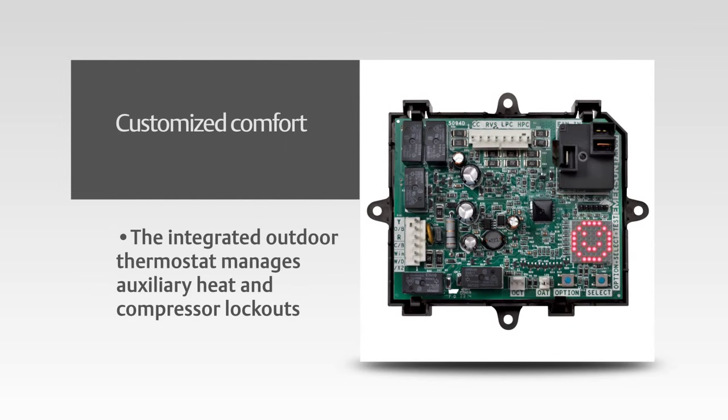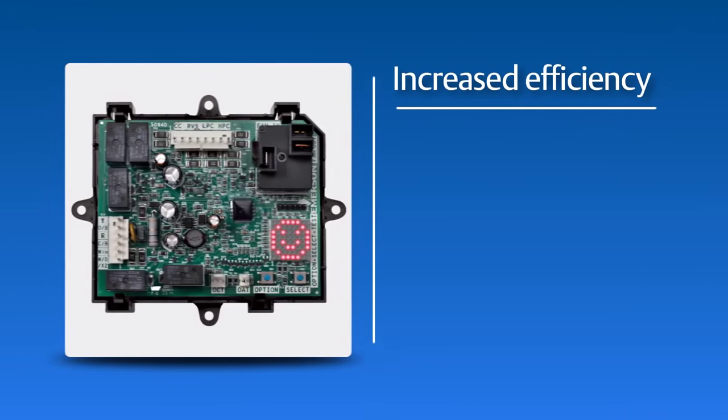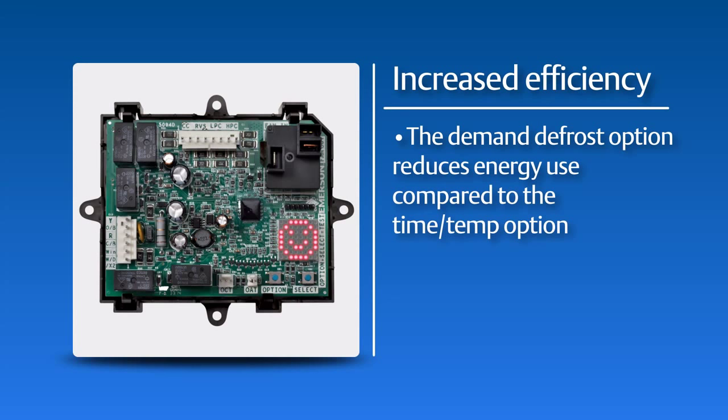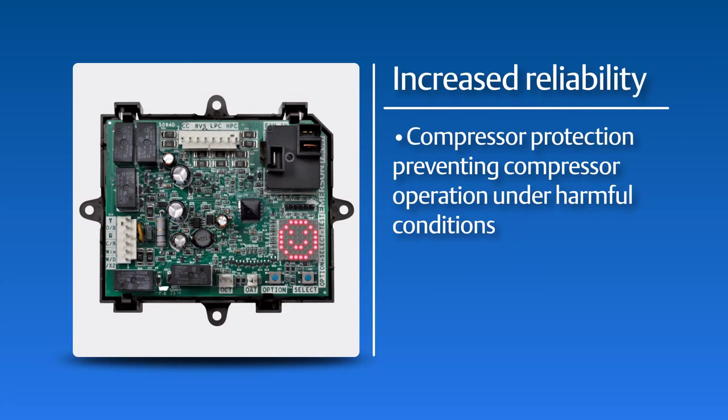The defrost control provides customized comfort with the integrated outdoor thermostat that manages auxiliary heat and compressor lockouts. It also provides increased efficiency with the demand defrost option that reduces energy use compared to the time temperature option. The defrost control has increased reliability, featuring compressor protection, which prevents compressor operation under harmful conditions.